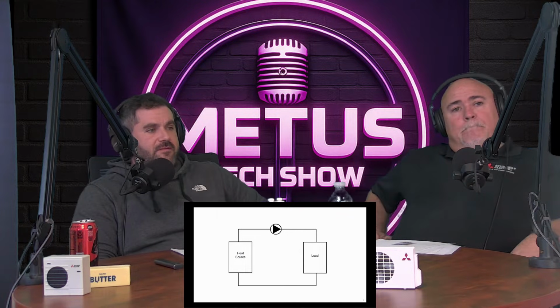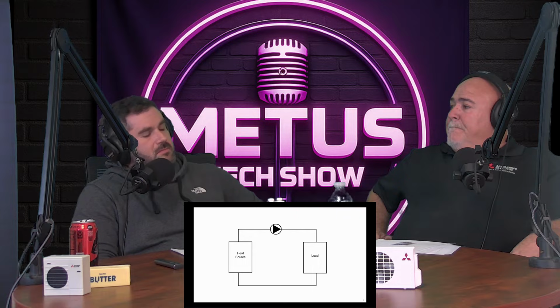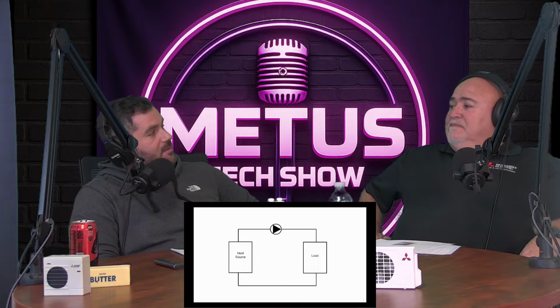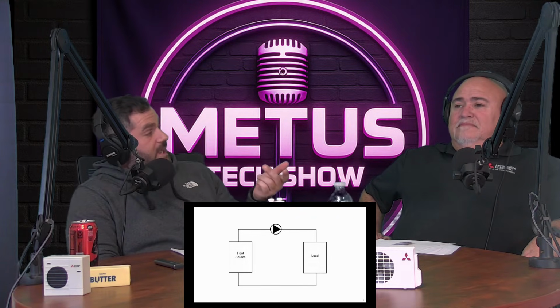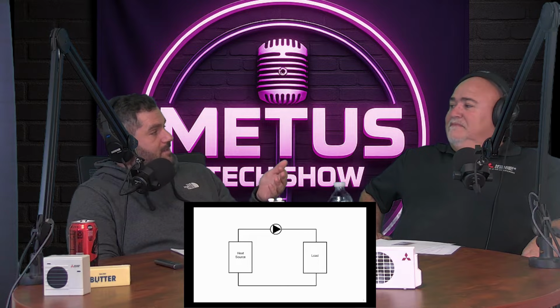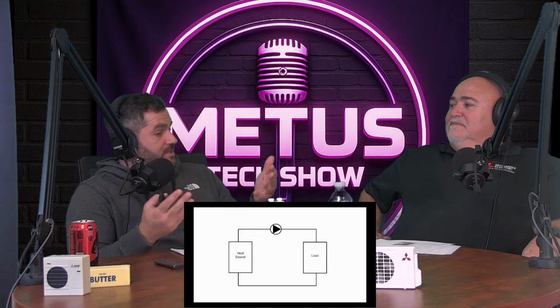So that's what I wanted to start with, which is basically what the hydronic loop looks like. Essentially you have your heat source, which could be literally anything. It could be an oil burner, which is what I started with, which is just a pistol style burner. It atomized the fuel at a high PSI, high pressure, would turn it into a mist, like a spray bottle at constant speed. Then there was a little igniter, and the spark would go across it, would ignite, and it goes into typically a cast iron heat exchanger. And that cast iron just heats up and it stores heat really well.